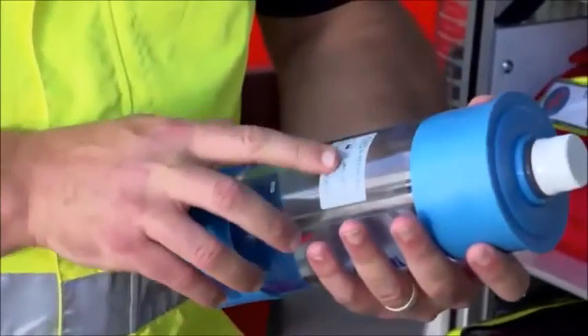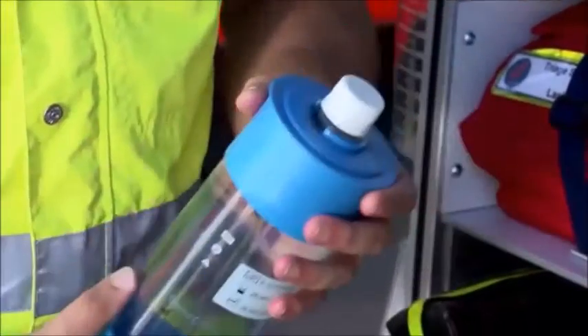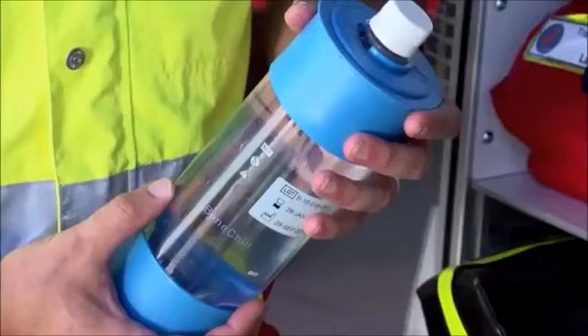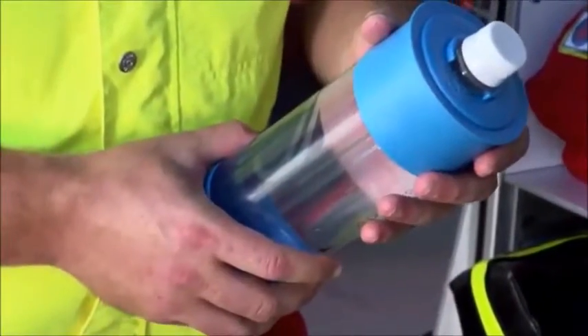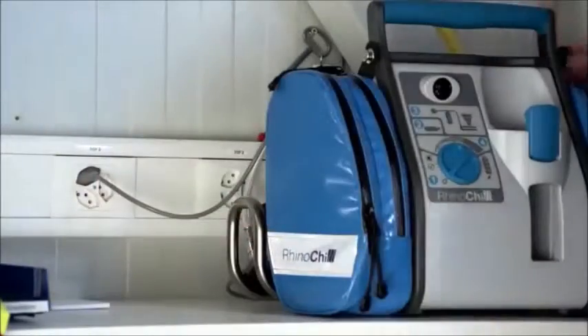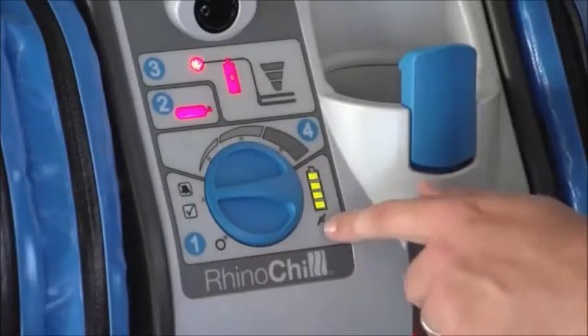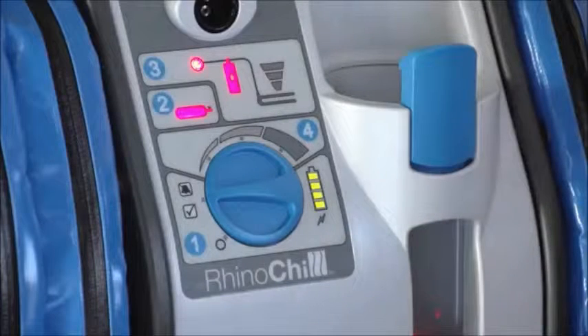The coolant is a completely inert liquid that evaporates easily and forms a fine vapor when pressurized gas is passed through the system. It is supplied in 1-liter single-use bottles that last approximately 30 minutes at the medium flow rate setting. The control unit controls the flow rate of the coolant gas mixture and monitors the system status when in use. The unit operates from an internal rechargeable battery with sufficient capacity for a 4-hour runtime, but can also be powered from an external 12-volt DC power supply or the supplied AC power supply, making it suitable for use in all areas.